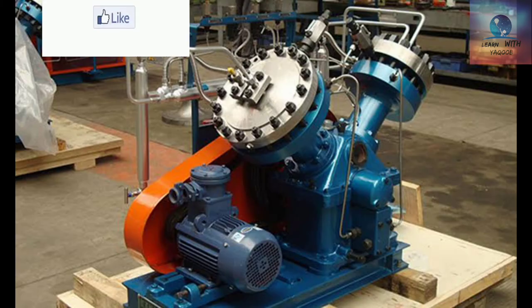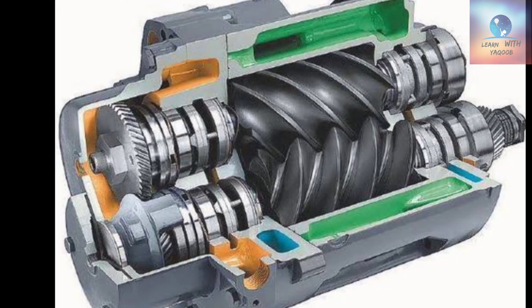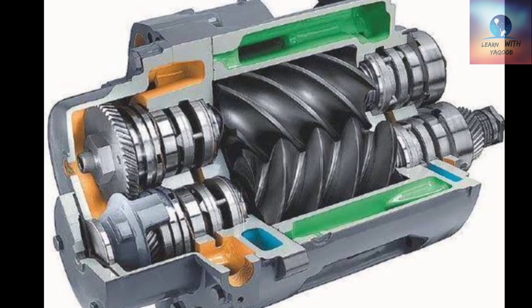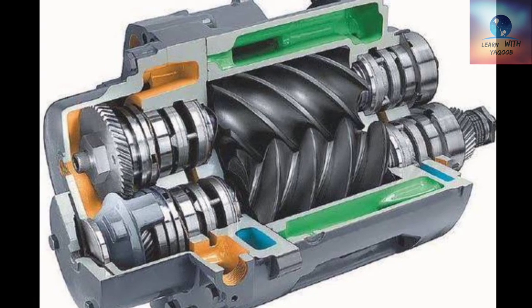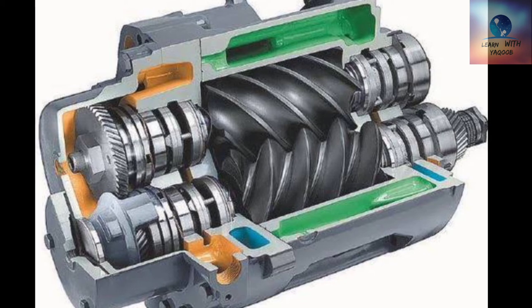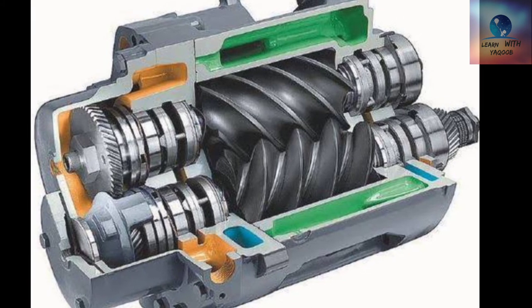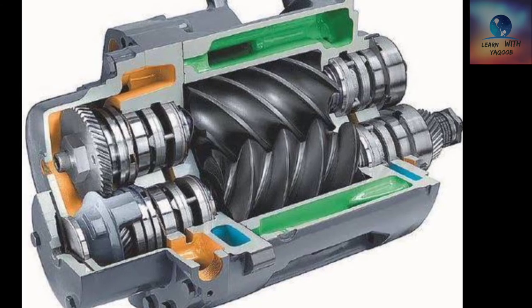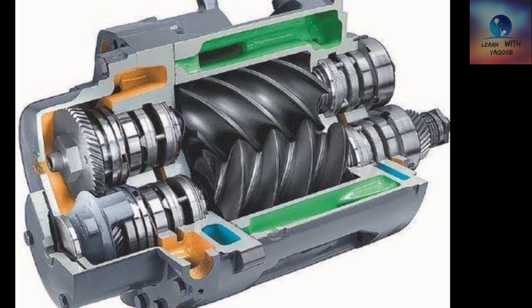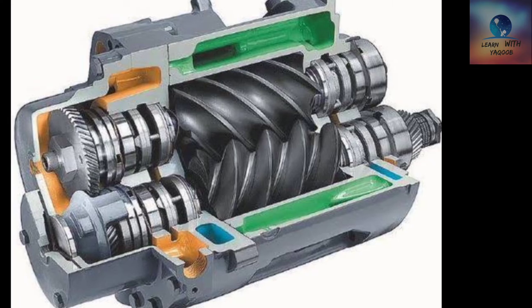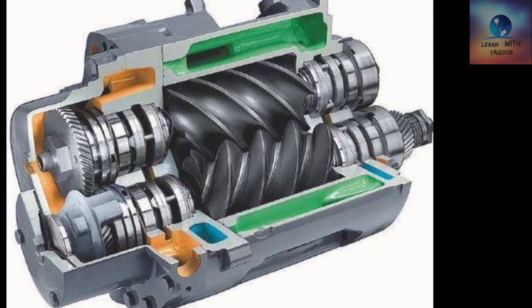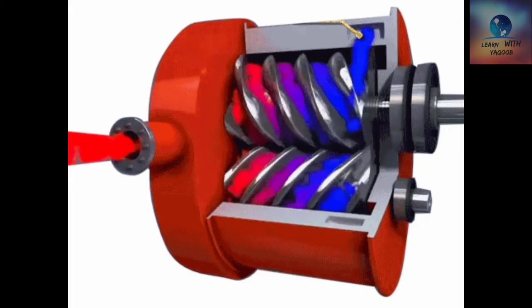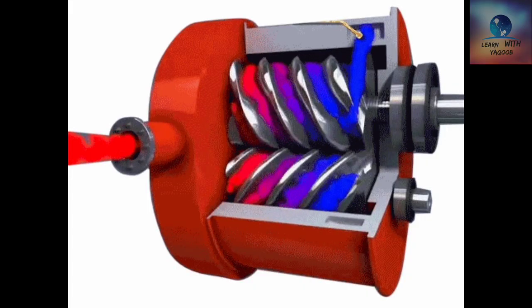Helical screw compressors are rotary compressor machines known for their capacity to operate on 100% duty cycle, making them good choices for trailerable applications such as construction or road building. Using geared meshing male and female rotors, these units pull gas in at the drive end and compress it as the rotors form a cell and the gas travels their length axially and discharge the compressed gas through a discharge port on the non-drive end of the compressor casing.